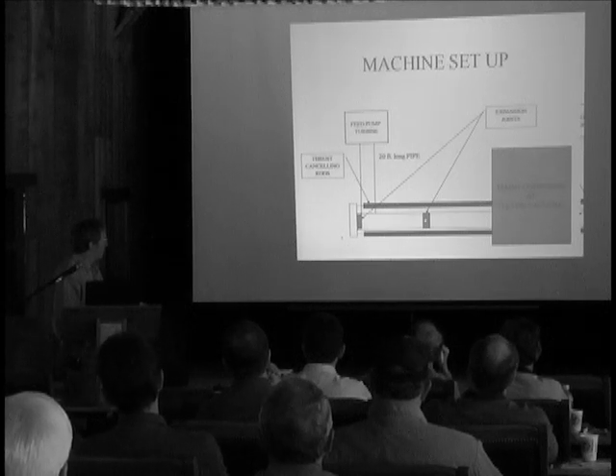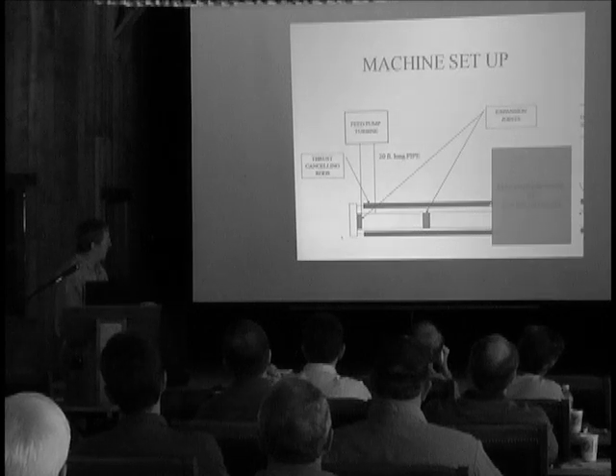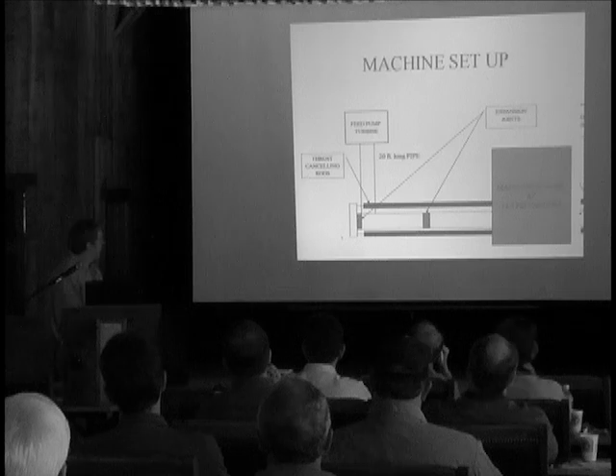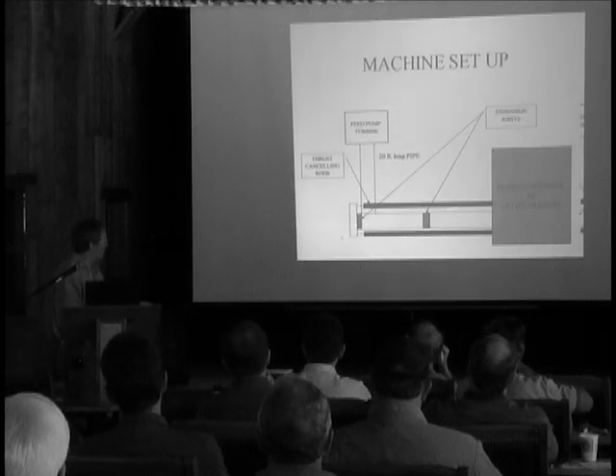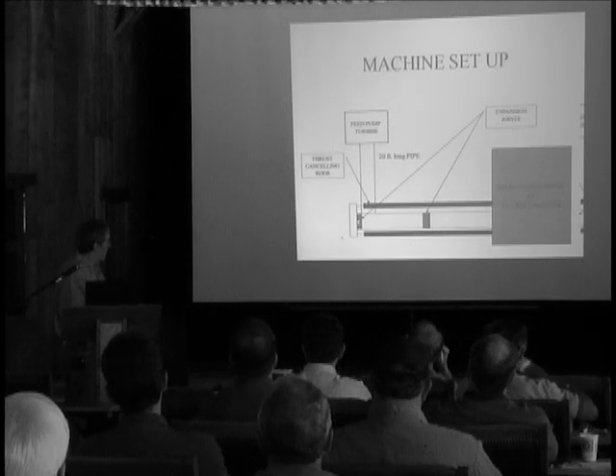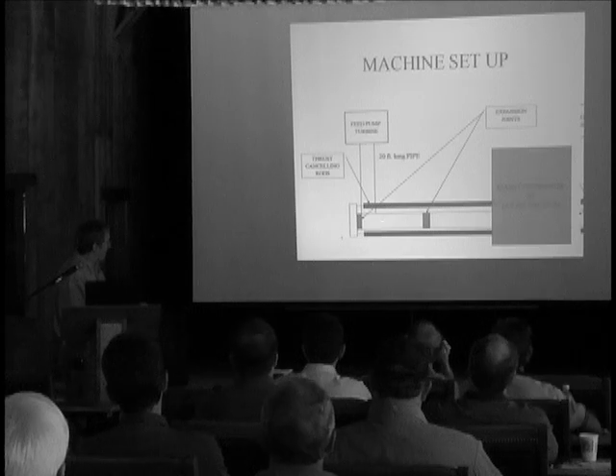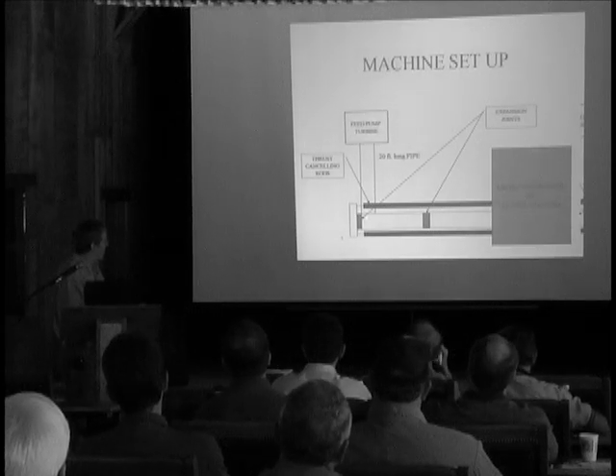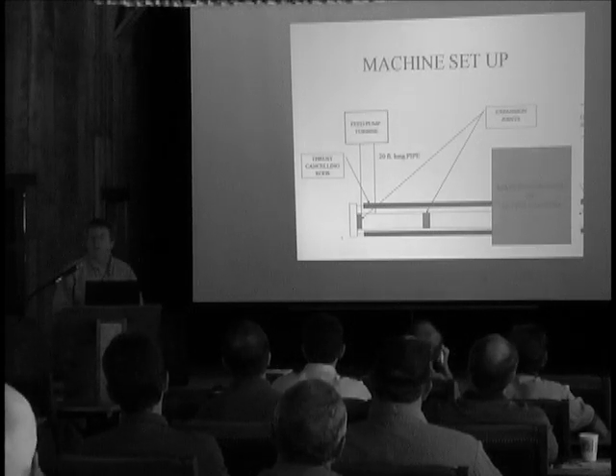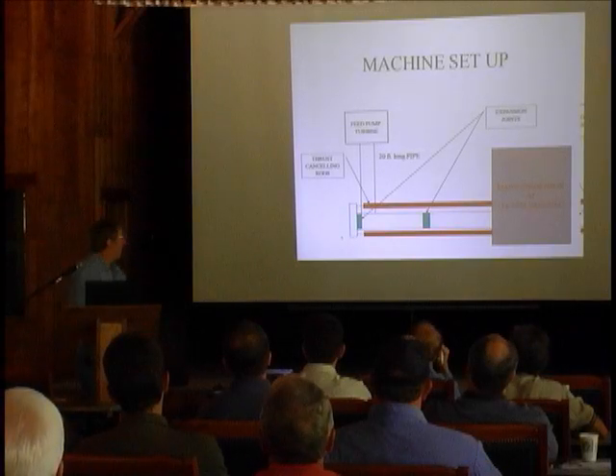piping. Then you have an expansion joint here and an expansion joint here. And then you have these thrust canceling rods that go out here, these really are pipes. And then you have this going over the end. And the whole purpose is so things can move around and back and forth. And with these expansion joints, you're not getting any movement of the section of pipe right here, which goes up to the feed pump turbine, because you obviously don't want to do that.